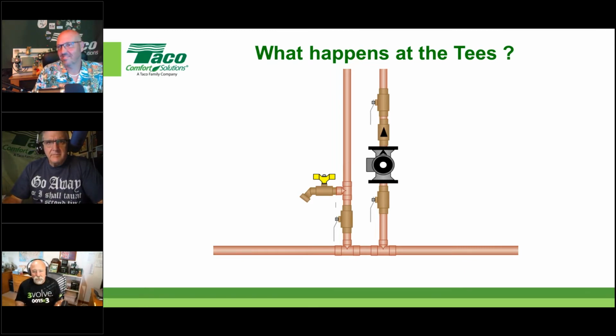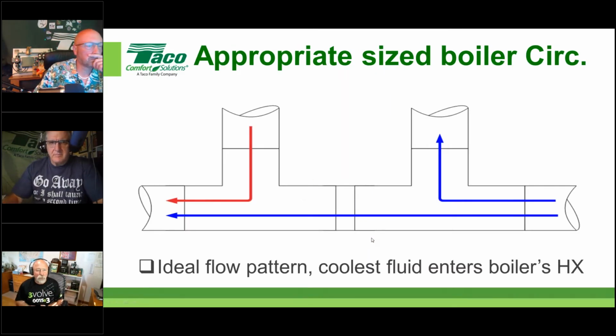And it's kind of a gradual thing. We'll focus in on this set of T's right here. So I'm going to blow this up so you'll know what I'm talking about. The ideal flow pattern is to have the coolest water back to the boiler, right? Everybody knows that - it's a modulating, condensing piece of equipment. We all know that anything under about 130 F is good.